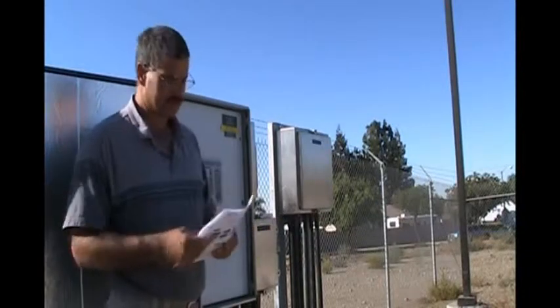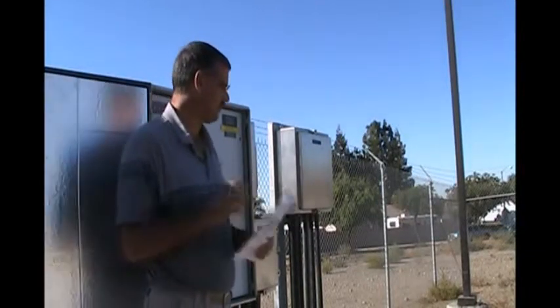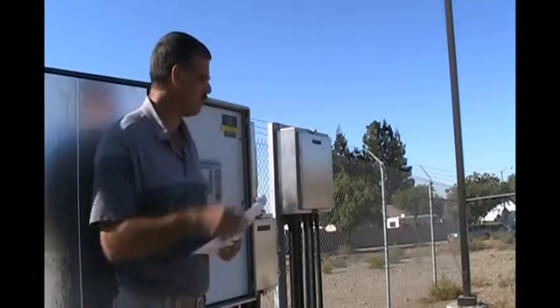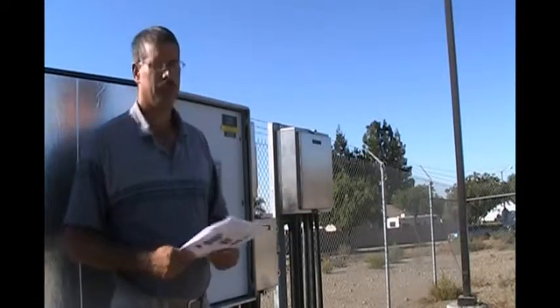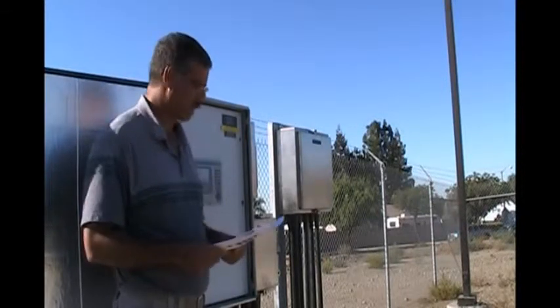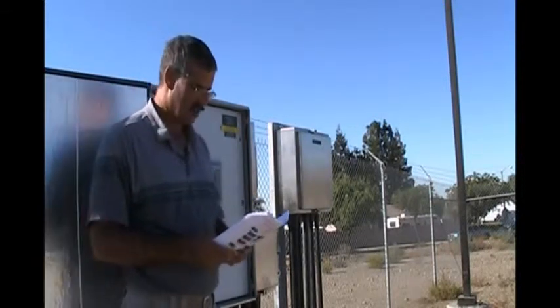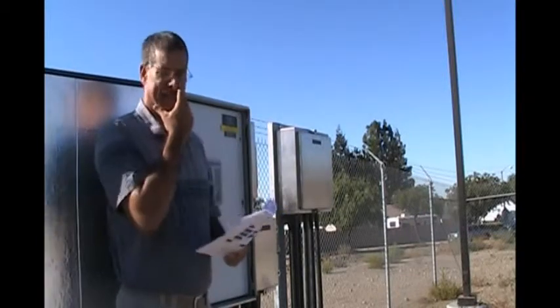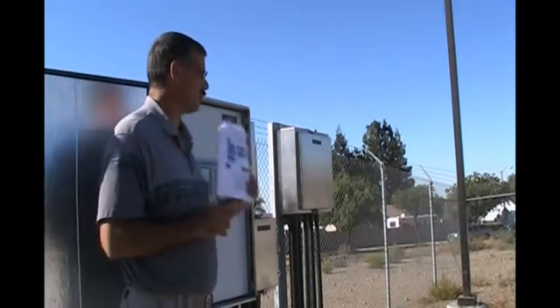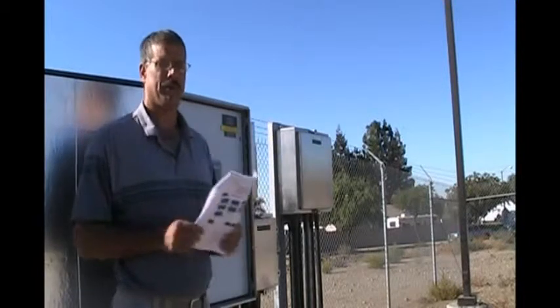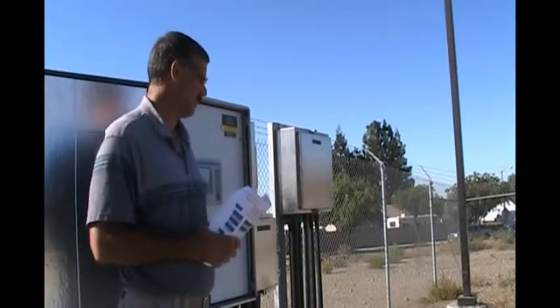Now, there are 2 set point screens. When you first enter the set point go-to button, it'll take you to the first screen, and it brings up all the values for your alarm set points. So you'll see on the left-hand side we have our pressure alarms. We have a high, a low, and a low. Now, the spec on this was that the valve will only operate if the pressure is above 60 psi.